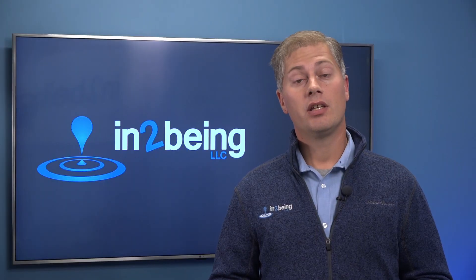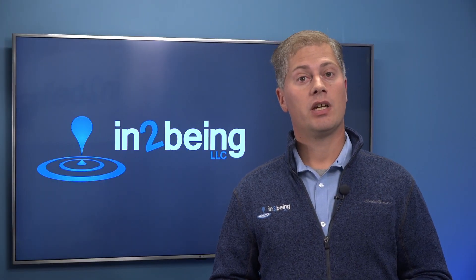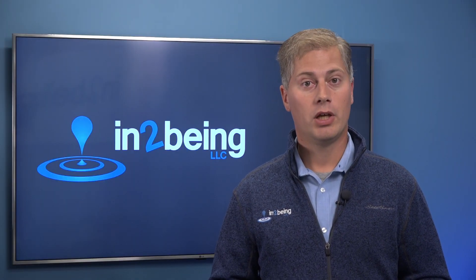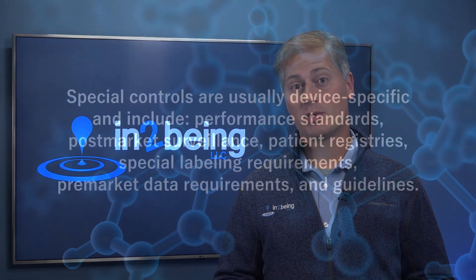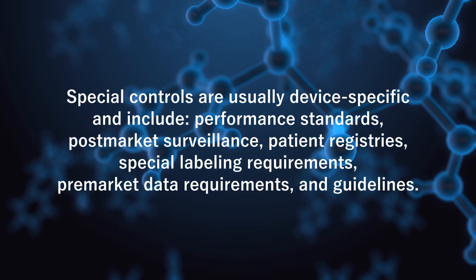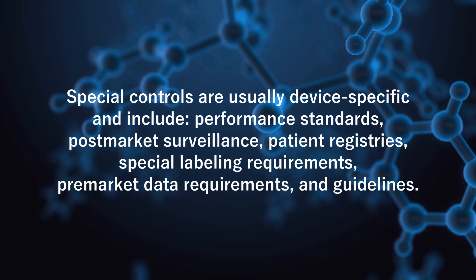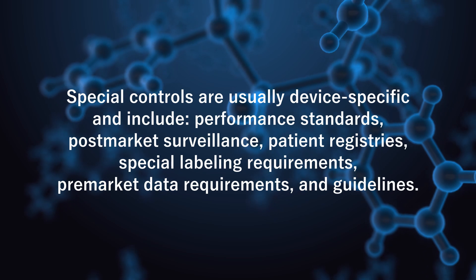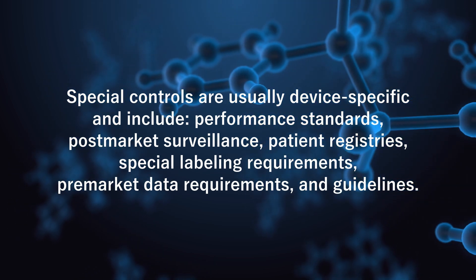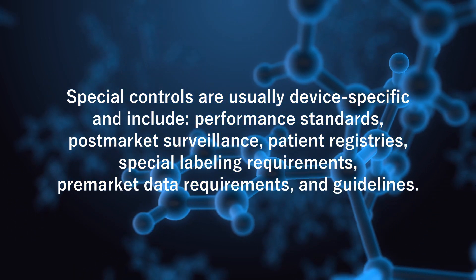Many class 2 devices require special controls in addition to general controls. These ensure safety and efficacy when general controls alone are insufficient. As the FDA says, special controls are usually device-specific and include performance standards, post-market surveillance, patient registries, special labeling requirements, pre-market data requirements, and other guidelines.